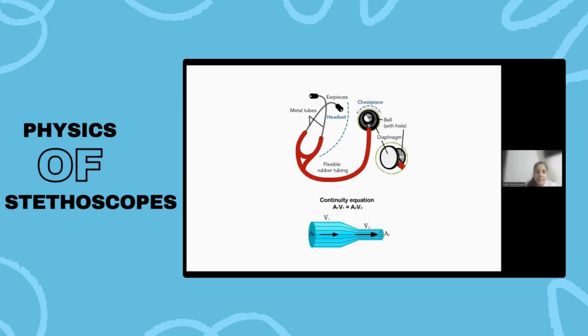Similarly, when it travels through the tubing, since it is made of rubber, it has low acoustic impedance. Acoustic impedance is basically the measure of how well sound waves can travel through a particular material. Since the tubing is made of rubber and its acoustic impedance is low, the sound waves are well contained inside the stethoscope itself. So it travels smoothly through the tubing to the earpiece. Finally, when it reaches the earpiece, it blocks any external or background noise and directs and focuses the sound wave into the doctor's ears directly, so that the internal body sounds can be heard very clearly.